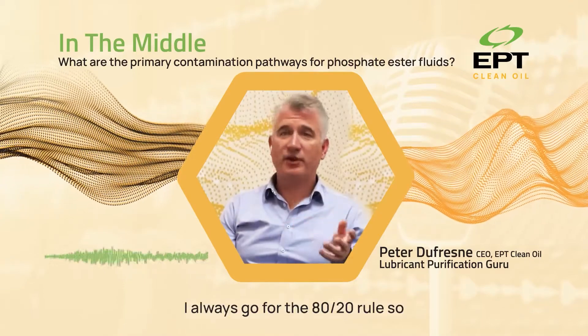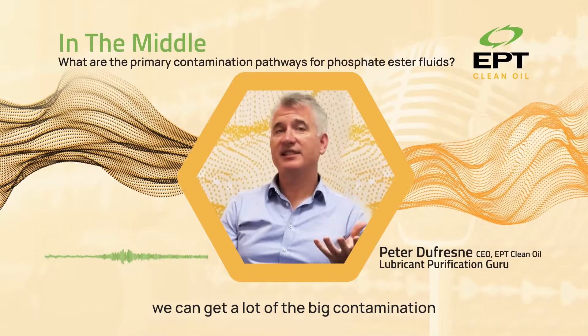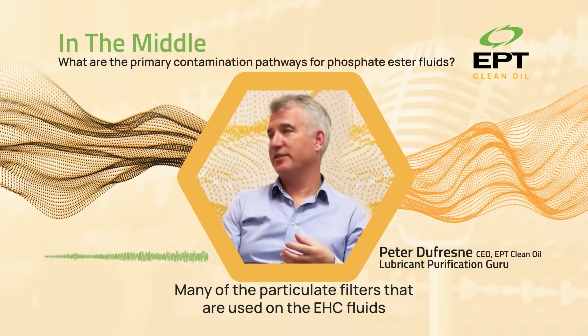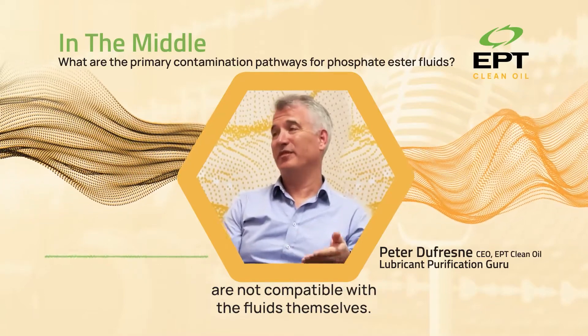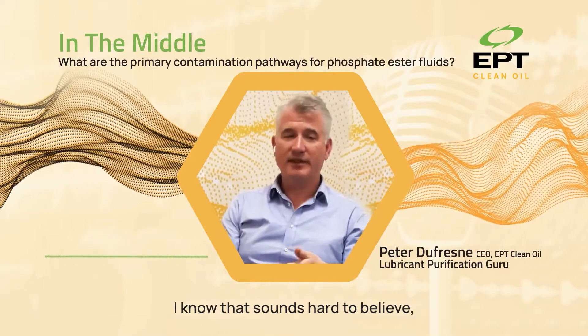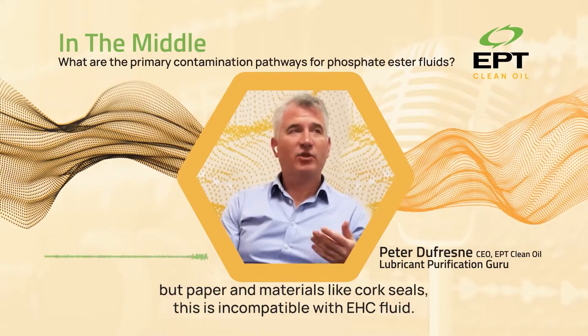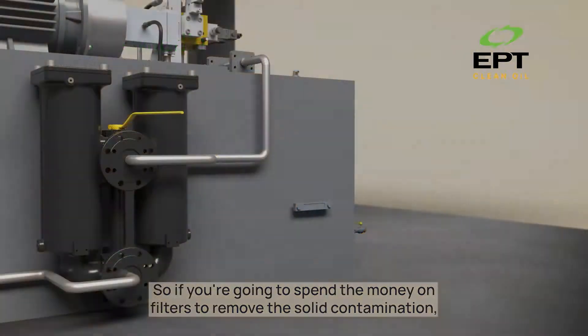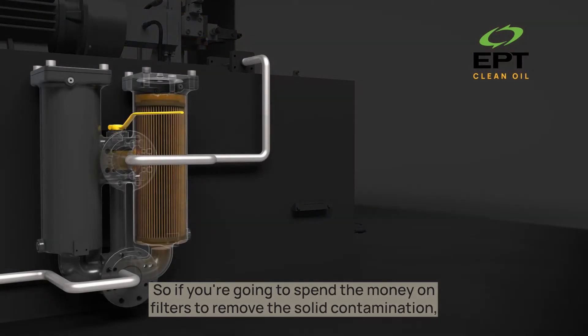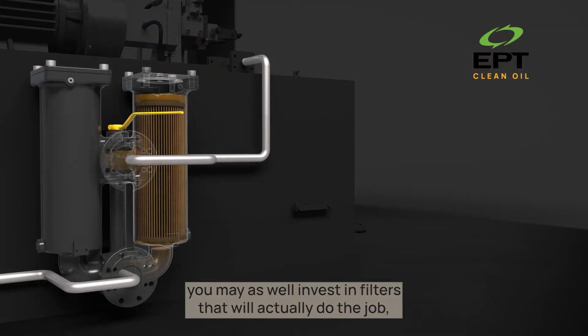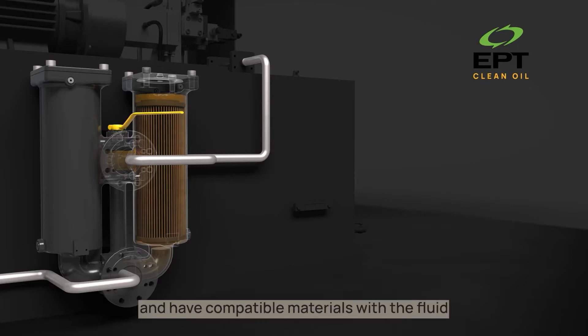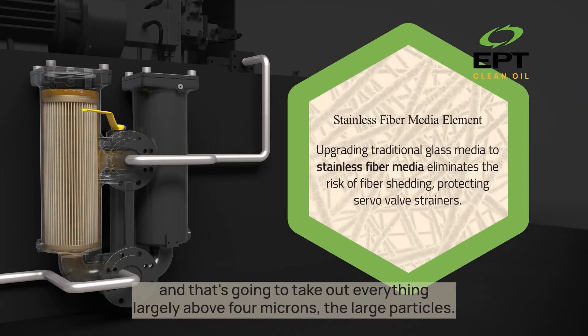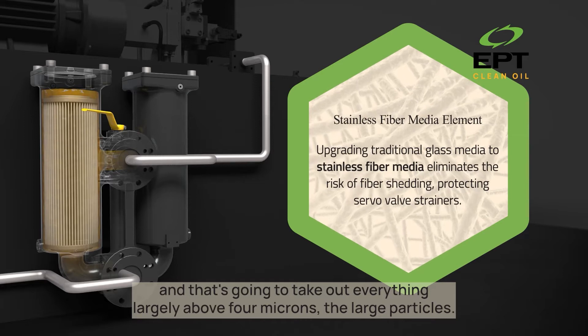I always go for the 80-20 rule, so we can get a lot of the big contamination out of the system just by using an upgraded particulate filter. Many of the particulate filters used on EHC fluids are not compatible with the fluids themselves. Paper and materials like cork seals are incompatible with the EHC fluid. So if you're going to spend the money on filters to remove solid contamination, you may as well invest in filters that will actually do the job, have compatible materials with the fluid, and have a high efficiency rating — taking out everything largely above 4 microns.